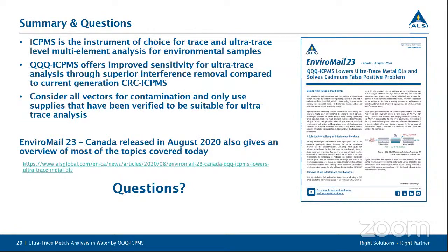So to quickly summarize, ICPMS is the instrument of choice for trace and ultra-trace level multi-element analysis in environmental samples. Triple quad ICPMS offers improved sensitivity for ultra-trace analysis through superior interference removal compared to current generation collision cell ICPMS. And when doing ultra-trace metals analysis, you need to consider all vectors for contamination and only use supplies that have been verified to be suitable for ultra-trace analysis.